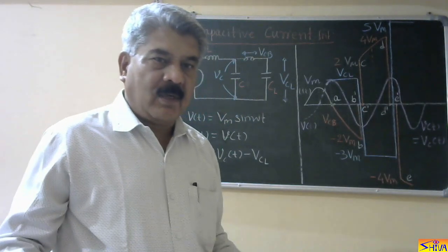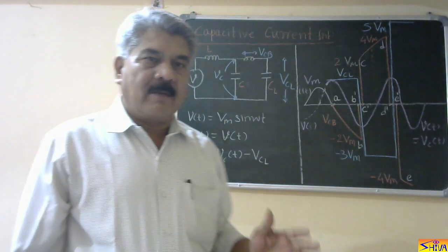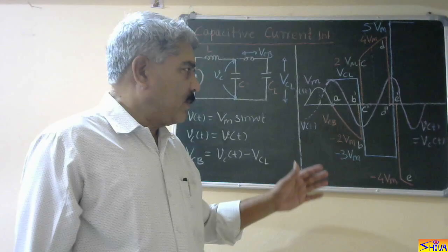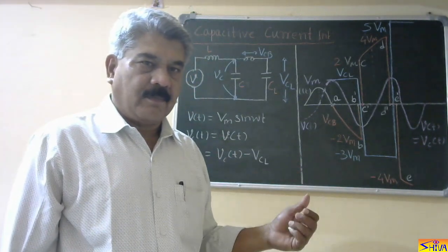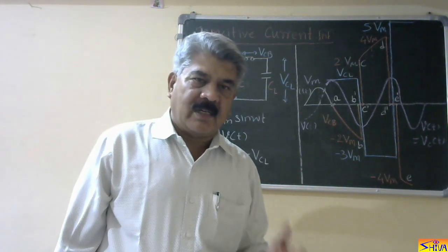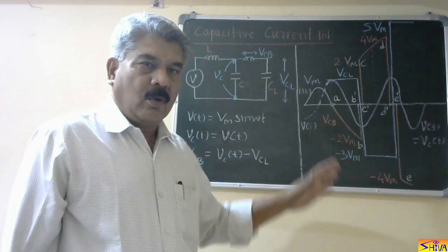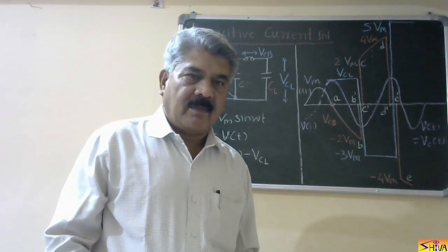This is very high voltage, and hence we can say that when circuit breaker is interrupting low capacitive current, very high switching over voltages are developing across circuit breaker poles. So circuit breaker has to undergo one of the worst conditions when it is interrupting low capacitive current or low inductive current. Now what is the remedy over this?